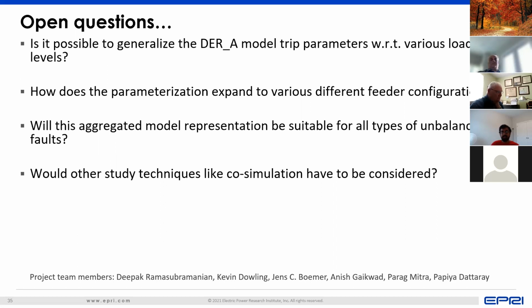And what that means is that one voltage event at that higher transmission level can really cause a wide amount of DER to react, if those settings are not configured properly. A single fault at the transmission level could now result in a large amount of DER tripping, which is something we are very concerned about from the transmission side.